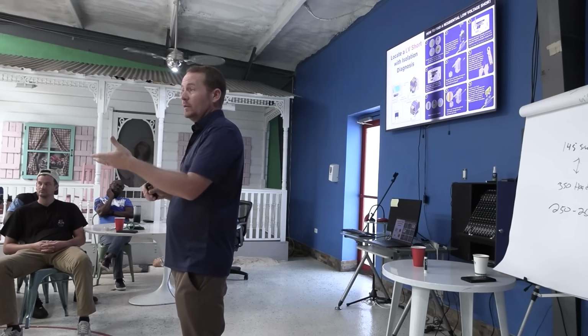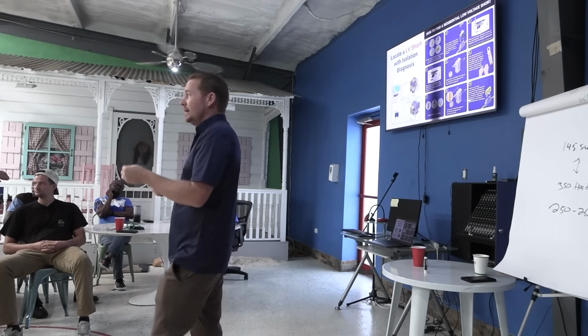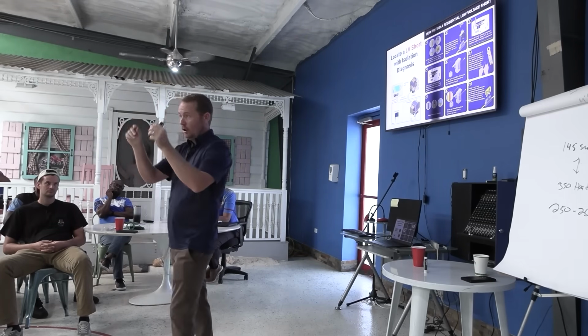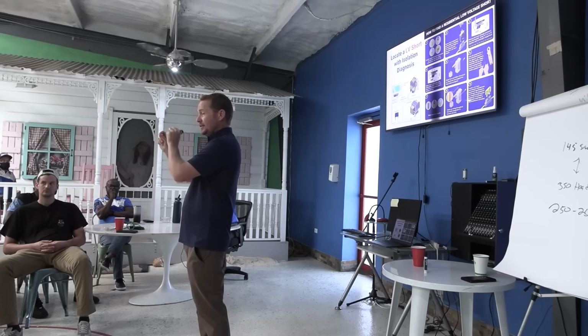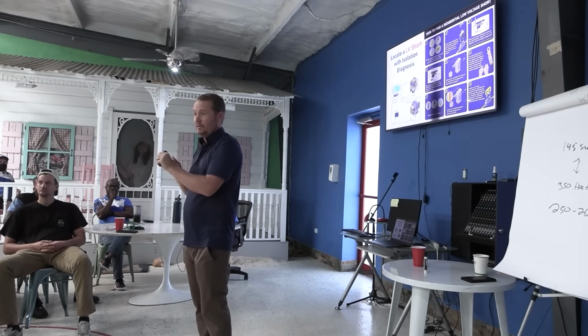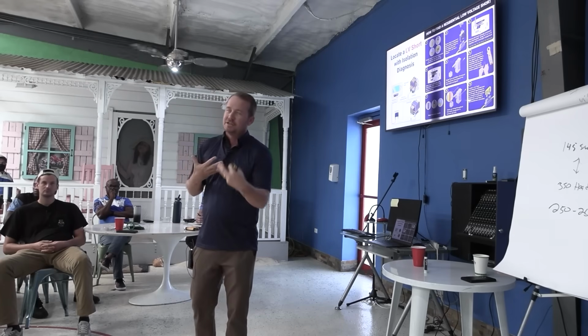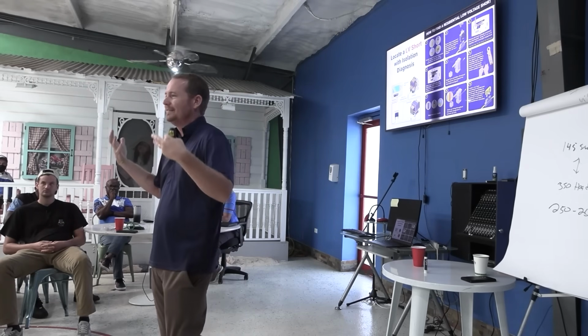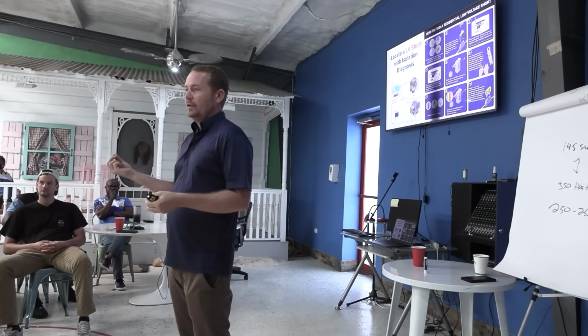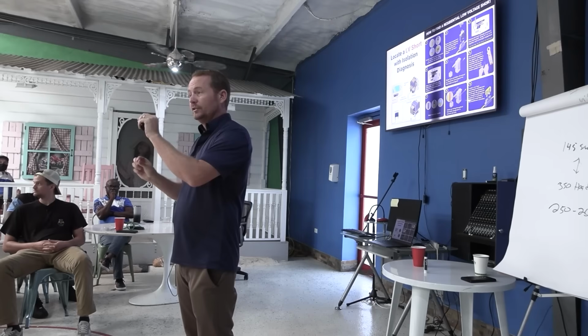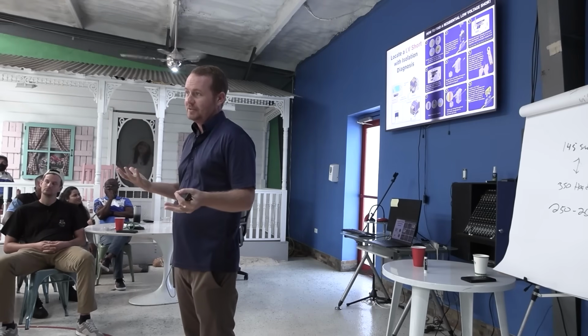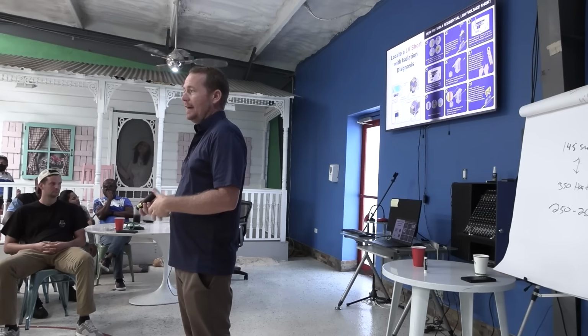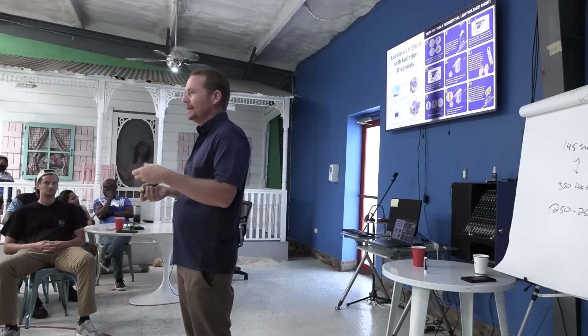Sometimes you can use other ones to get by, but the right way to do it is to isolate all the conductors on both sides, then check them to each other and to ground. That's where the limitations of an ohm meter come in. With a megohmmeter you can check under higher voltage and really see if any are compromised, which is handy. If you don't have that, you're just going to have to replace the conductor.